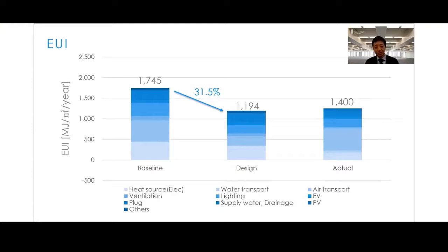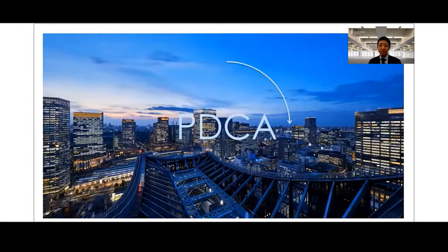While many reasons can be considered for this, one of the major reasons is that the demand control ventilation was disabled with the intent to maximize the flow rate as part of pandemic prevention. Also, we have to admit that the initial year after completion is presumed to reflect a lack of tuning for actual usage and conditions. Currently, monthly commissioning meetings referring to various operation data, including those presented today, are held for improvements. We think that this PDCA cycle after completion is a very important process to truly realize a high-performance building.